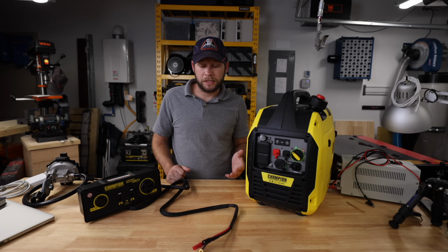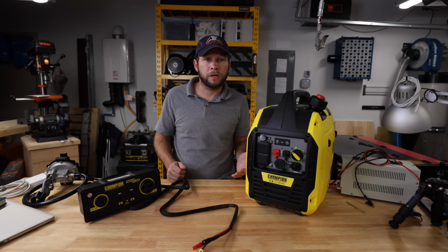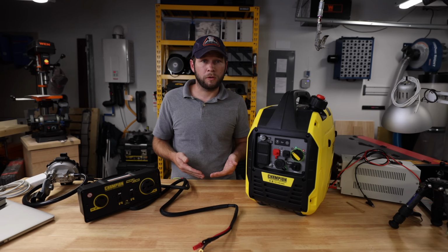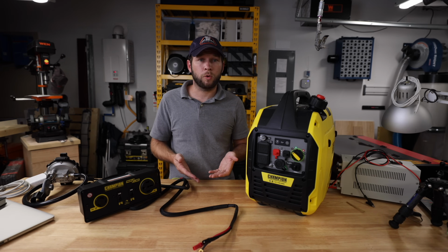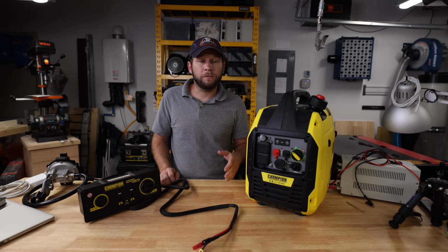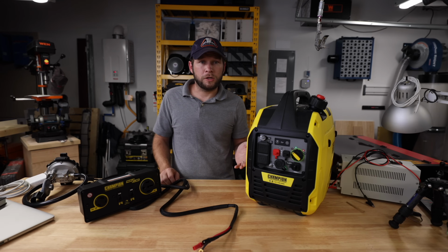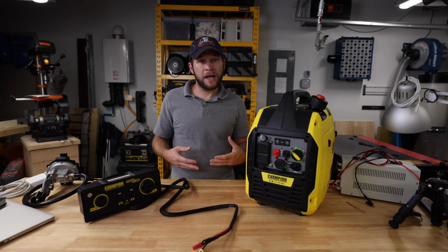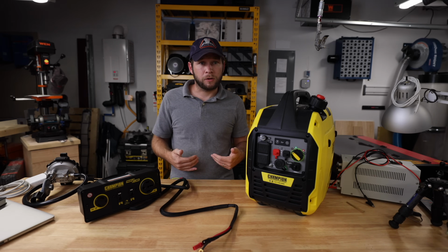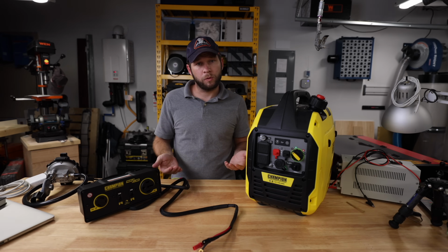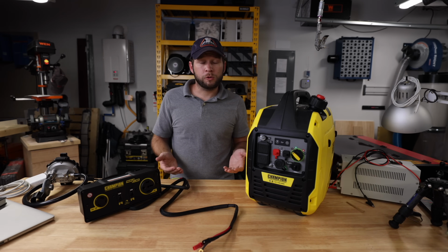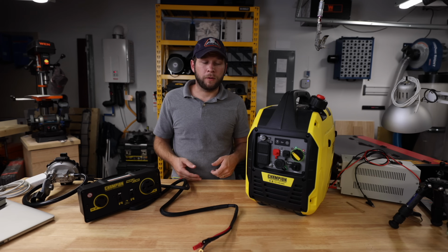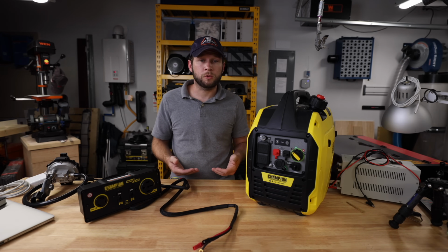The reason for this is because they cancel each other out, so they don't put excessive power on the neutral. The neutral in these wires can't carry any more current than each of the conductors individually. So if you have a 20 amp circuit and you go to neutral, that neutral is also carrying 20 amps. Now, with these circuits, since they're out of phase, the red and the black cancel. So if you have 20 amps on the black, 20 amps on the red, then the neutral actually doesn't see any power at all. If you have 10 on one and 20 on the other, the neutral only sees 10 amps.